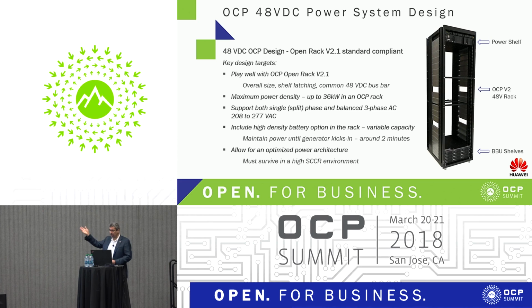This is the rack we didn't manufacture. That's a version 2 rack from a manufacturer. Our equipment just bolts into it. And what you see there is our power supply on top and battery shelves on the bottom. We wanted to have high power density, 36 kilowatts, support both balanced 3-phase and single phase, and then have batteries in the rack, because again, this is part of the overall system efficiency. Put batteries in the rack, you can eliminate the entire UPS. UPS is gone. You have the generator, but we're backing up the power until the generator kicks in, so there's no UPS.